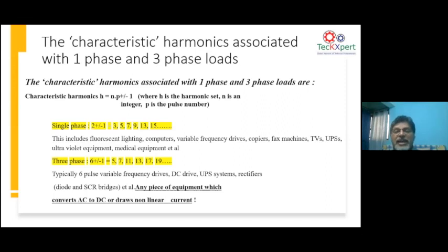Now, non-characteristic harmonics are not defined by this equation. Non-characteristic harmonics are what? That is the even harmonics, or the interharmonics, or subharmonics. These are all non-characteristic harmonics. So that is why this equation is only used for characteristic harmonics, and any single phase or three-phase electronic load, if it is working correctly, is only supposed to generate characteristic harmonics, not non-characteristic harmonics.